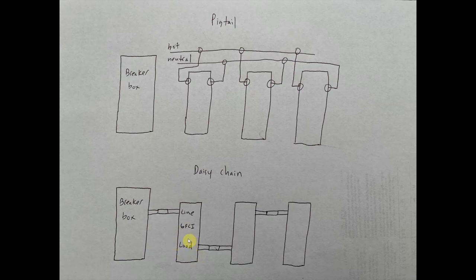So you're going to have again six wires in the box. Now what happens is basically the power to this outlet here is actually being powered from the outlet that's upstream. So you're going to have again six wires in this box: black, white, ground, and again the other side black, white, ground. And let's use this as an example - this is going to be a standard outlet, so it doesn't matter which two screws you put it on because it's going to be powered by this receptacle or outlet.